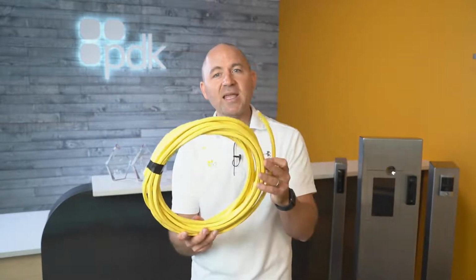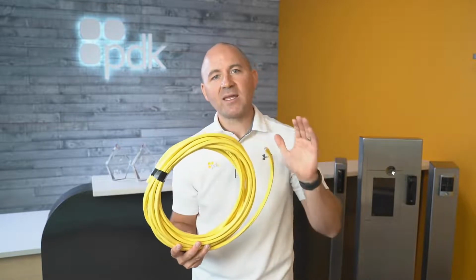Being consistent, in my opinion, always running a banana cable or a braided cable for your access control is a win every single time because consistency wins, even if you're not going to utilize all of the wires available. This banana cable runs anywhere from 50 cents, I even just bought some Plenum stuff that ran about 70 cents a foot. By the time you calculate all the individual strands, you're not saving time. You're always better off, even though it has a few extra cables you might not be using on a specific door. It's always best to be consistent.